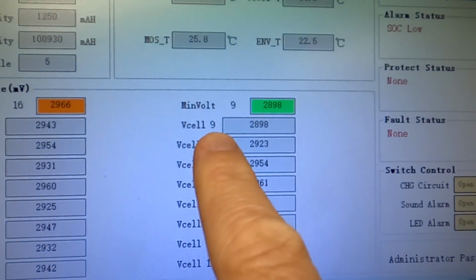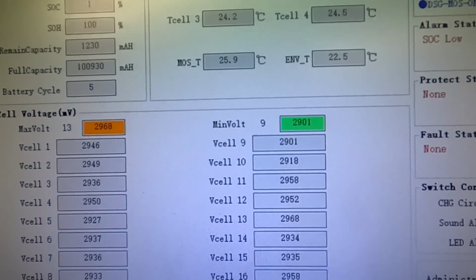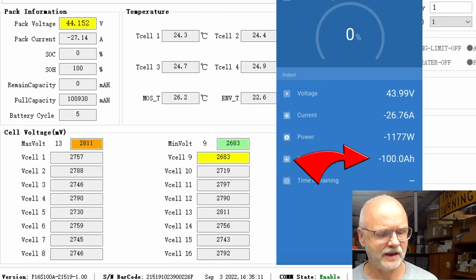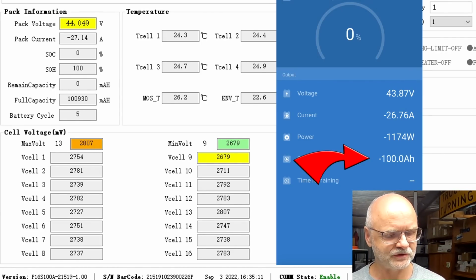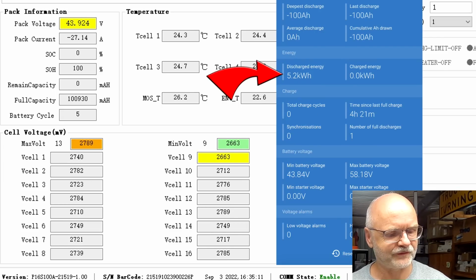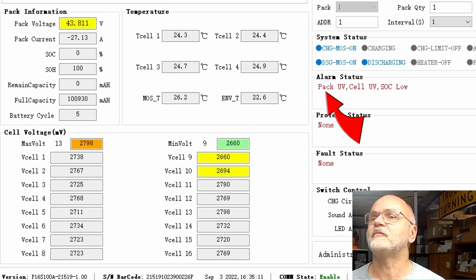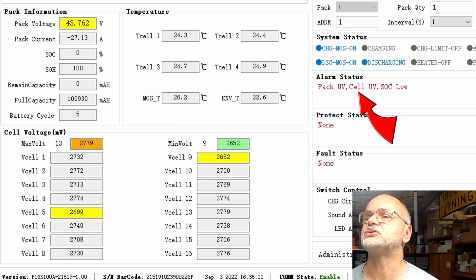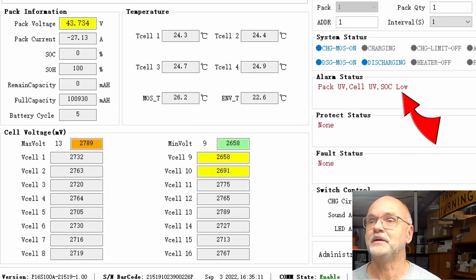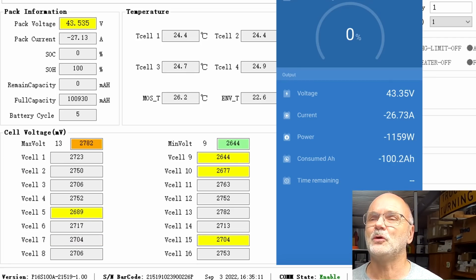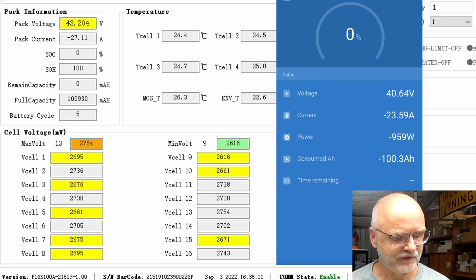For quite a while, cell number 9 has been our lowest again, like in the first test, so it might be worth testing cell 9 specifically and doing a full capacity test. Okay, 100 ampere hours - we've met our specifications. 5.2 kilowatt hours, 2.65 volts, and we have a pack under-voltage, a cell under-voltage, and a low state of charge alarm. But as you can see, cell number 9 isn't far from all the other cells - they're following fast. We've got cells 1 to 6 now with an under-voltage alarm, and that's it.